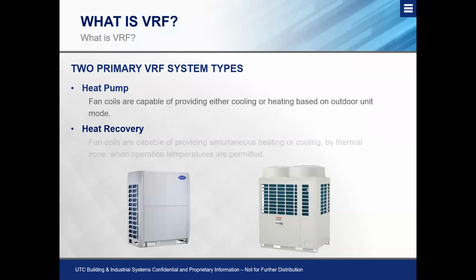Now, on the other hand, the other system type that we have is what we typically associate with those VRF systems, which is the heat recovery. Okay, so these are going to be those fan coils, cassettes, high walls, ducted units that can have that simultaneous heating and cooling need. And that's done in terms of a branch box or a flow selector, which essentially is comprised of a solenoid valve, a tube and tube heat exchanger, and some form of control wire that's connected to it to be able to communicate from the indoor unit to that specific port to open up individual solenoid valves to allow hot gas into a coil and return liquid, and allow liquid to come out and return suction gas, depending on whether we're in a heating or a cooling mode.